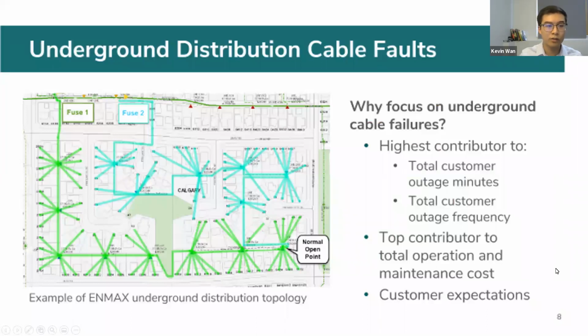So one area of concern we've had in the past few years is underground cable faults, also known as cable failures. Some of the reasons why we're focusing on underground cable failures are because they've become the highest contributing outage cause to total customer outage minutes and total outage frequency, also known as SAIDI. Cable failures are a top contributor to total operation and maintenance costs. And to meet high customer expectations, where there's a lower tolerance for long outage durations. These are the reasons why we focused on cable failures.